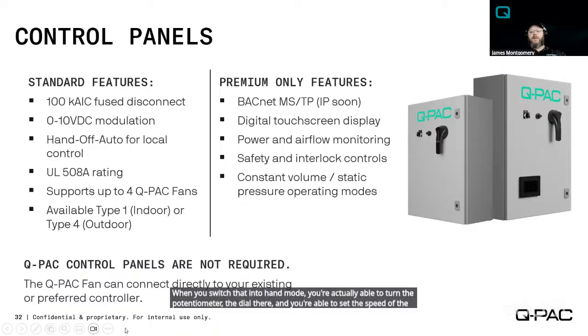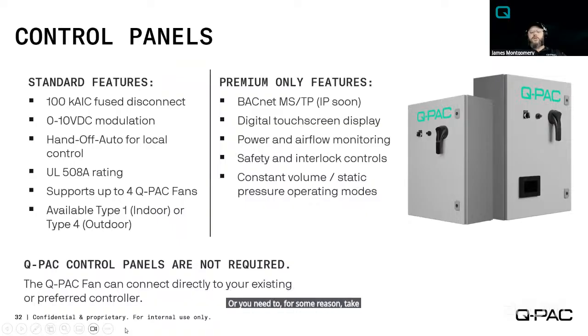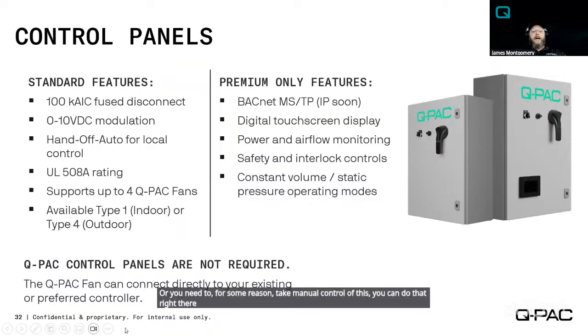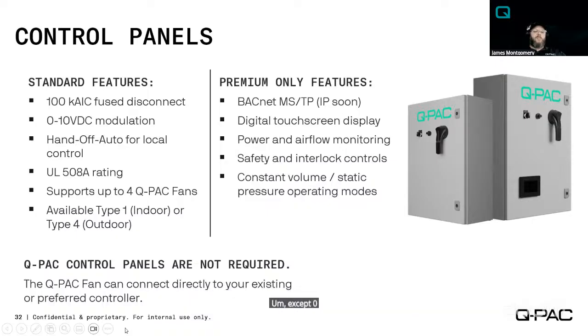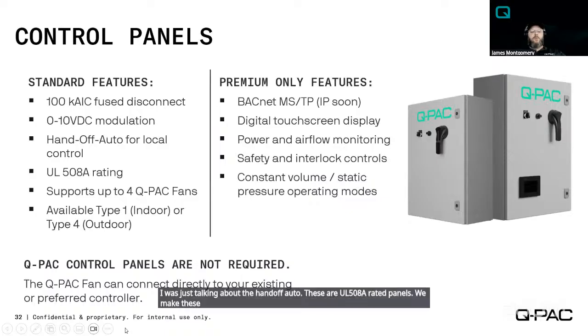So in the event of a loss of controls, or you need to, for some reason, take manual control of this, you can do that right there at the panel. And the standard features for our control panels: 100 kAIC fused disconnect, accepts 0 to 10 modulation. That's that speed control that we talked about. I was just talking about the hand-off-auto. These are UL 508A rated panels. We make these in-house here at Q-PAC. We're a UL 508A panel shop.